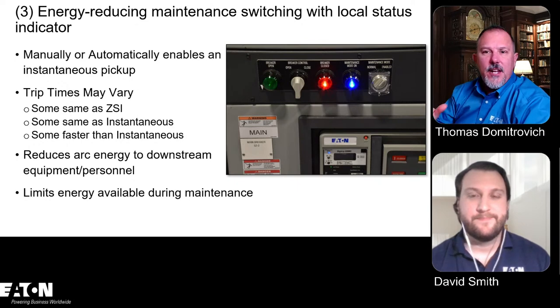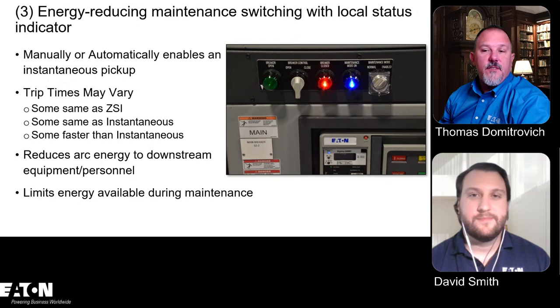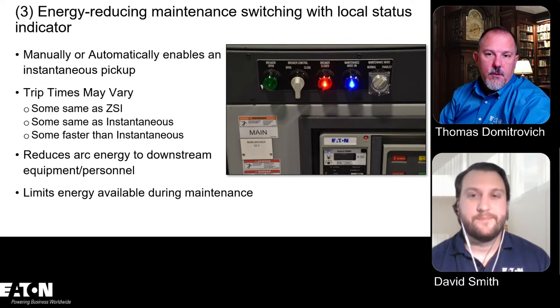Just like shutting off a breaker. When you want to establish an electrically safe work condition, you have to turn breakers off, and then you should lock and tag them out when you turn them off. So this is no different. If you're going to turn that arc reduction maintenance switch because you're working downstream, you're going to want to lock and tag it out.